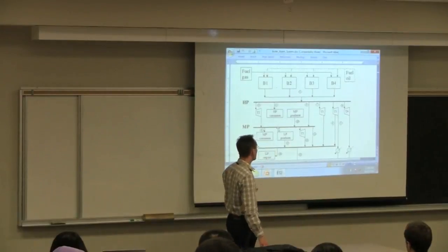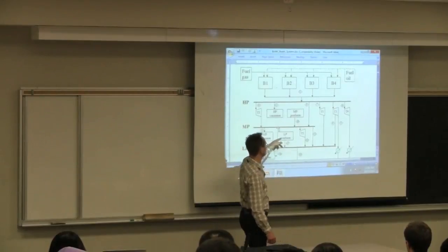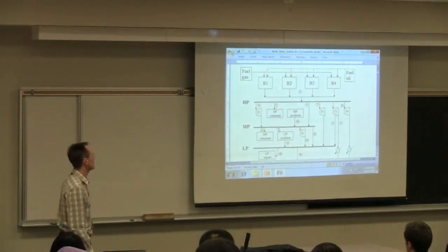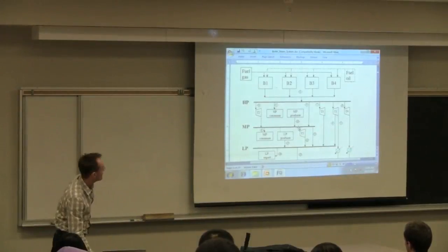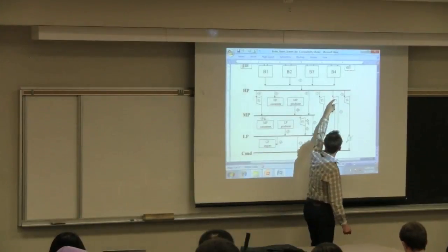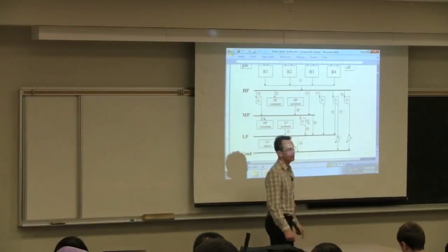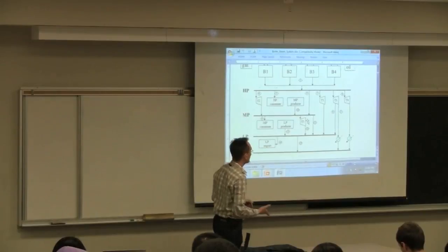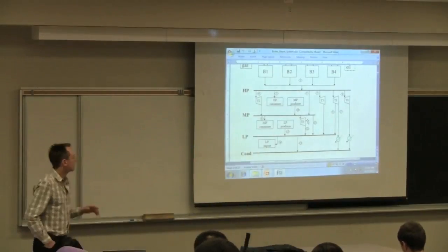to then let down some medium pressure steam down to low pressure. Or conversely, we may have a unit, a heat exchanger, that's producing medium pressure steam or low pressure steam for us that we pump back into those headers. So we get credits for those incoming steam as well, internally. We have heat exchangers out here in the site that will take this turbine, or here, either one of them. Those turbines then can be let down partially to low pressure steam, but we can even go through another heat exchanger and use that to heat up another stream in the site and then cool down our stream and just bring it down to condensate. So we have these multiple levels, and this can be pretty complex.